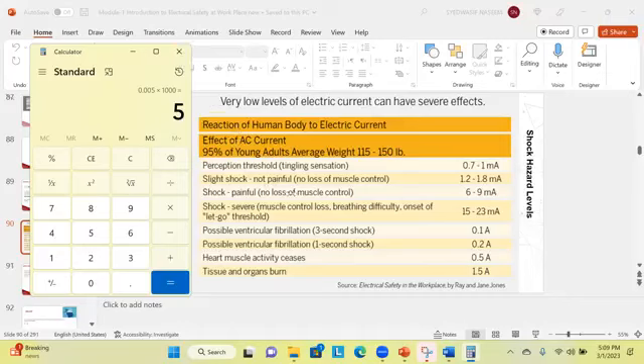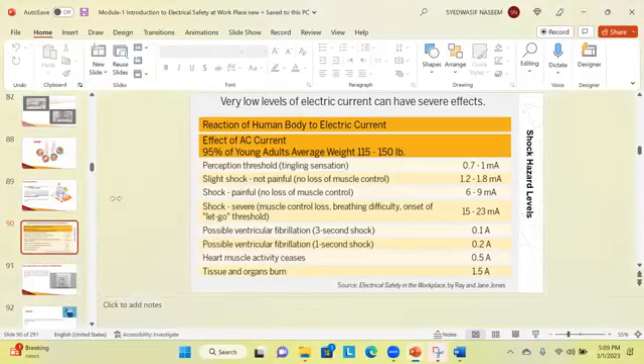Okay, so 5 milliampere, if we look here from 6 to 9 milliampere, the shock becomes painful. Muscle control is not lost, but now the chances are that a person will find himself in the danger zone. That's why in Article 105, on electrical safe work condition, it is saying that voltage equal to or greater than 50 volt shall be put into electrical safe work condition because of this reason.